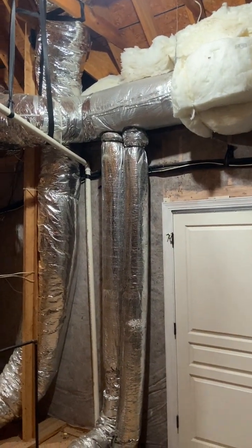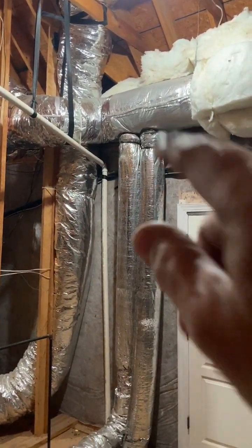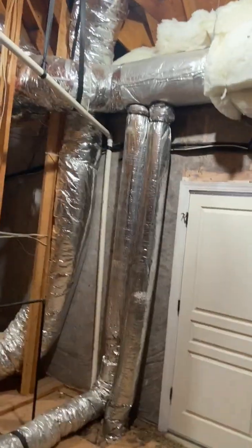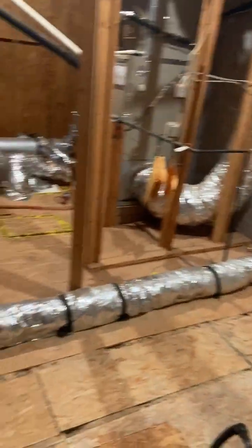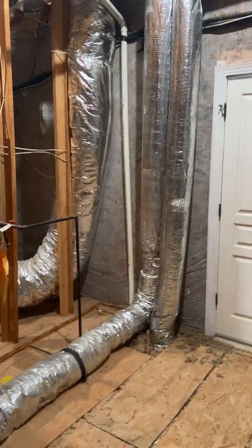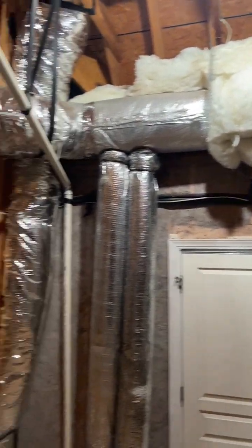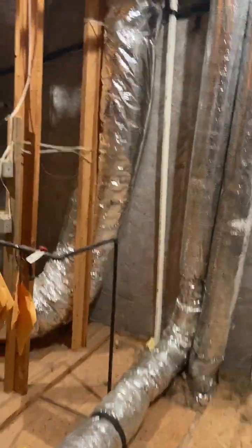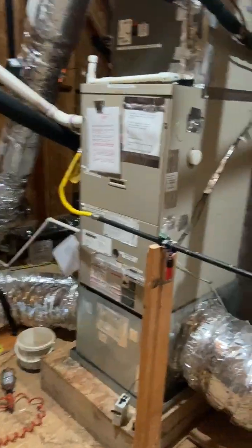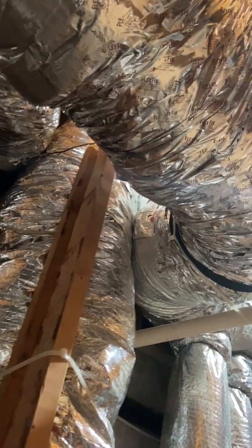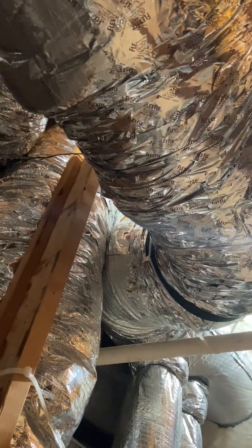Anyway, the main duct is this duct right here, and you can see these guys coming down off of it and feeding various rooms off the main duct. That's the main supply duct up there, and here it goes in. You have trouble seeing it, but right there is a zone control valve, and it's of the old style. That's one zone control valve, and those are 24 volt AC, and they're normally open.